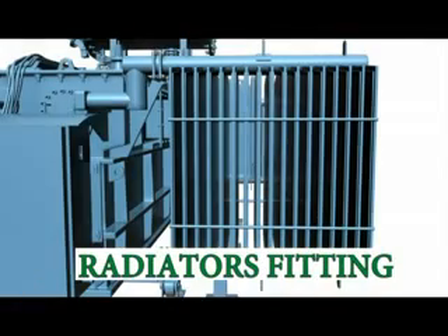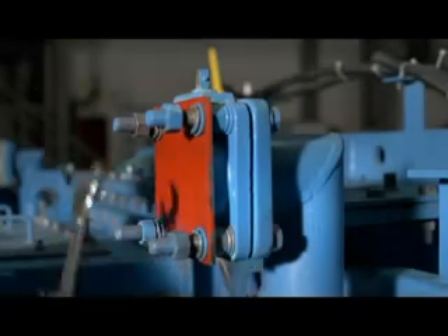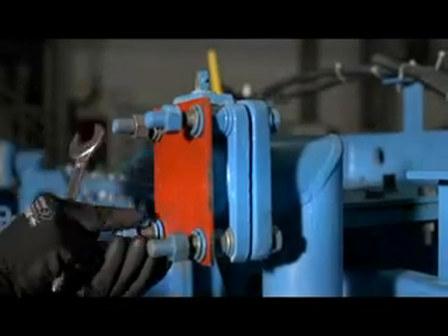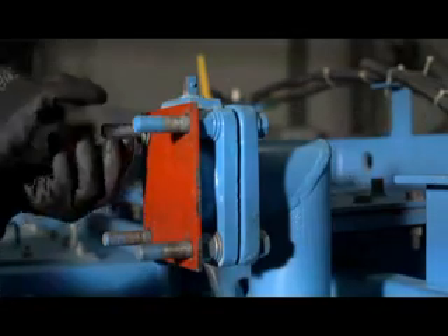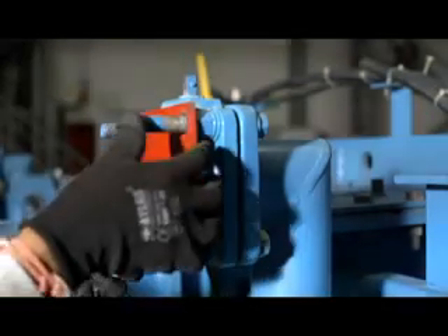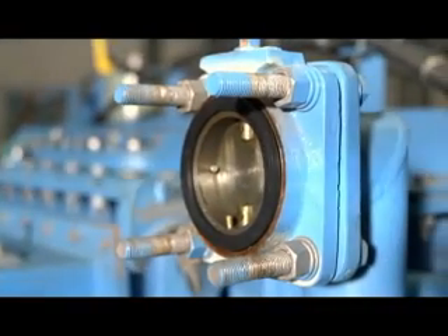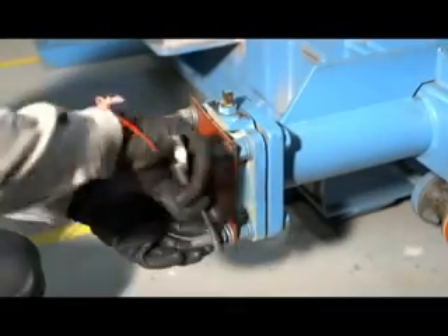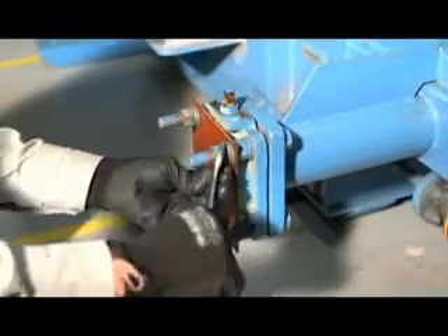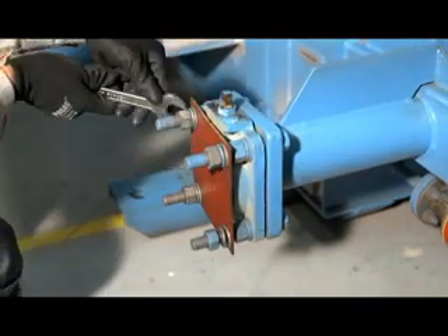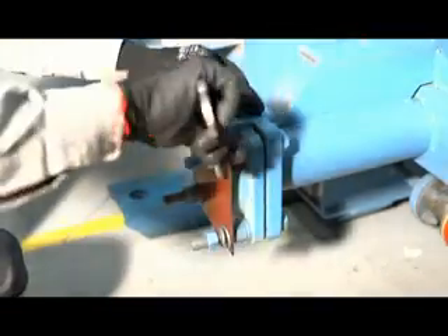Radiators fitting. Special care should be taken while removing radiators from crates, and the same care should be taken during handling and mounting the radiator bank. This is because any minor damage can initiate oil leakage from the bank. As radiator units are made from very thin steel sheets of metal for good conduction of heat from oil to air. After removing from crates, these radiators must be cleaned externally. These are also required to be cleaned from inside by flushing with transformer insulating oil.